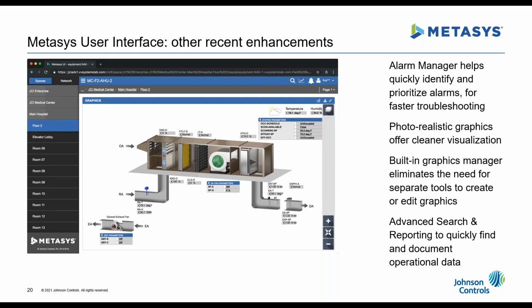Each of our releases adds to our user interface enhancements. Over the last few releases we've added things like Alarm Manager, which helps with nuisance alarms. Every system has them, though we're trying to eliminate a bulk of them with fault detection and fault triage. If you do get those nuisance alarms, you want them rolled up to a single line -- you don't want 50 different lines of nuisance alarms. Our alarm manager built into the user interface does exactly that: it rolls up alarms and helps you quickly identify and prioritize them, so you're not missing critical alarms among a whole bunch of nuisance alarm rows.